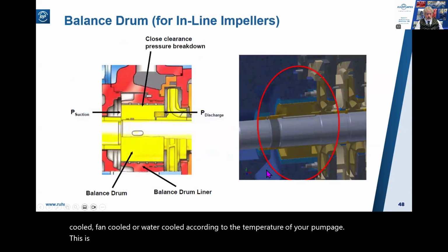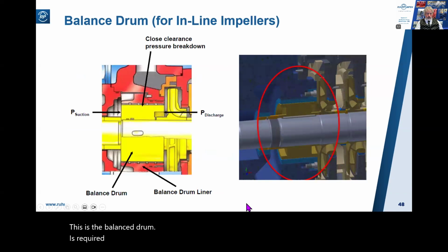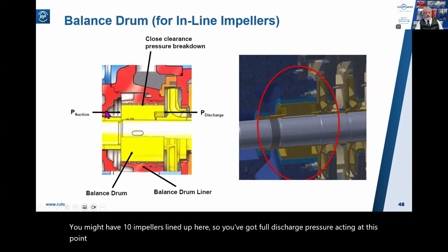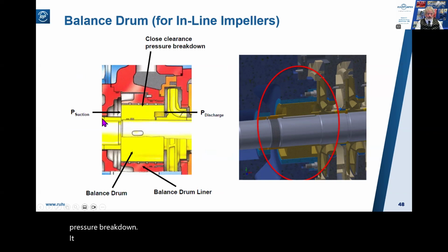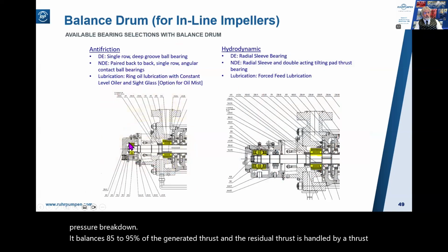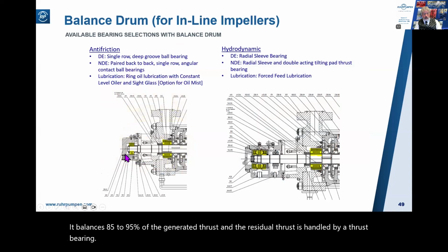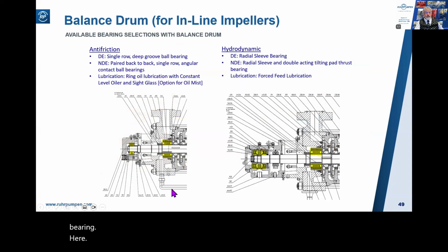This is the balance drum that is required for inline impellers. You might have 10 impellers lined up here, so you've got full discharge pressure acting at this point here. You've got suction pressure acting at this point, and across this labyrinth is the pressure breakdown. It balances 85 to 95% of the generated thrust, and the residual thrust is handled by a thrust bearing here. No axial movement, but the leakage increases with wear, leading to an efficiency drop and an increase in thrust.